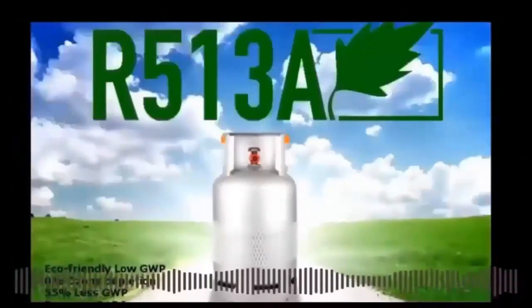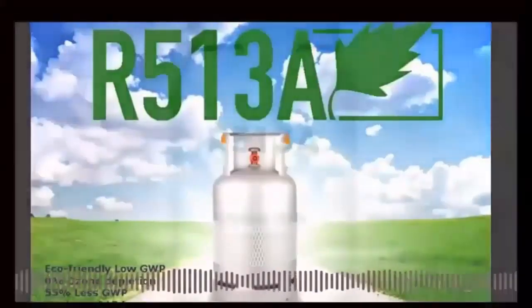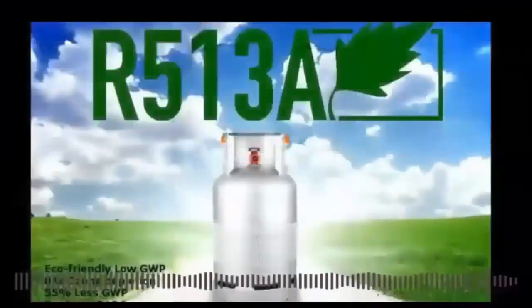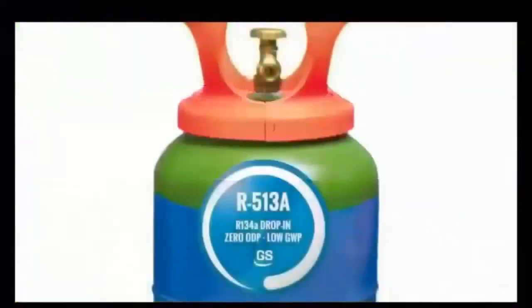R513A refrigerant has a GWP of 629, but has a weak point with slightly lower efficiency than R134a. R513A refrigerant is a drop-in, direct replacement for R134a in existing commercial and industrial refrigeration equipment, high and medium temperature, positive displacement and direct expansion.